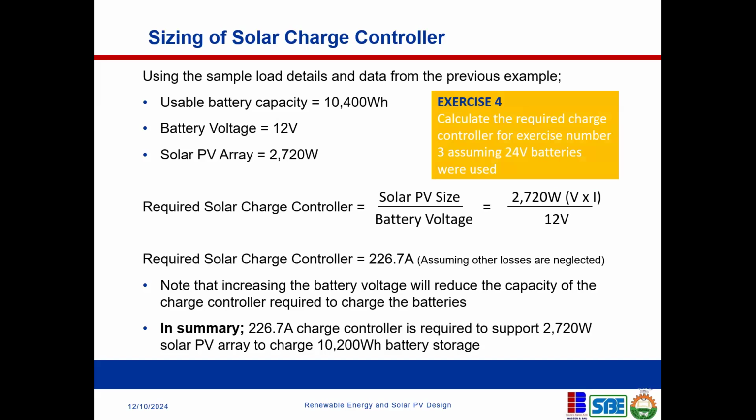Calculate the required charge controller for the exercise you did, exercise number 3, where you arrived at a 7,285.7 watts PV array. Calculate the required charge controller for that exercise, assuming you have 24-volt batteries. Please, let's quickly do this.